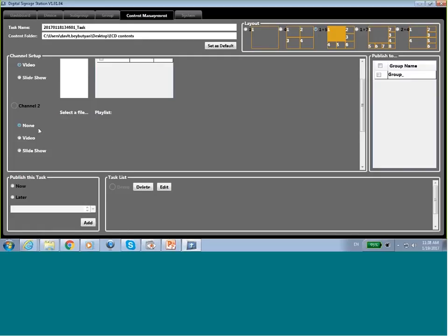We won't upload any content here. Yes. The reason is that if I want to add a camera to channel 2 or channel 3 and 4, we simply click None. We cannot add a video? You can add a video, it won't be an issue. The issue will be that the video will be lagging while showing on the monitor. Oh, because there are two streams trying to get to that same channel.